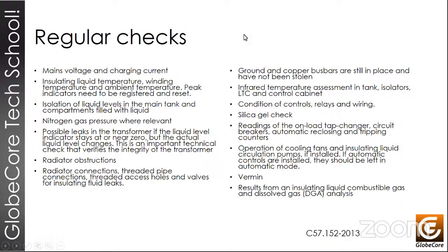Other things that we can check for are gas pressure, nitrogen pressure, possible leaks. We need to check radiators and the general cleanliness of the transformer. On several occasions, weeds or plants were observed in the radiators, which made them only marginally effective at reducing temperatures. Also, radiator connections must be checked for leaks. It's also necessary to do infrared analysis or scanning to see that temperatures at certain points are not entirely out of control. Some of the other things to check are the controls, the wiring, and if the transformer has a breather, then one must ensure that the silica gel in that breather is in good condition.